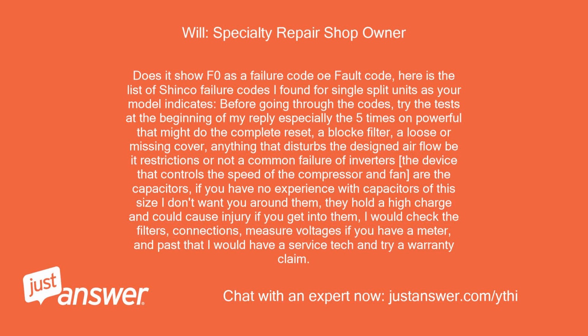Does it show F0 as a failure code or a fault code? Here is the list of Shinko failure codes I found for single split units, as your model indicates. Before going through the codes, try the tests at the beginning of my reply, especially the 5 times on powerful. That might do the complete reset. Also check for a blocked filter, a loose or missing cover, anything that disturbs the designed airflow, be it restrictions or not.